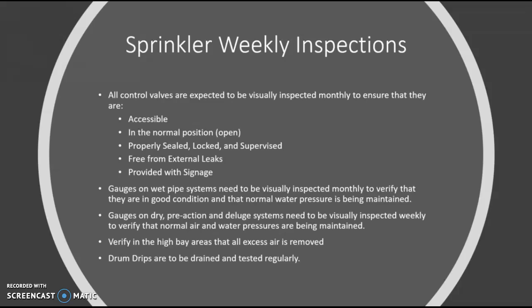And to do this, all the drum drips in the system will have two valves, an upper and a lower. And the upper valve will then be closed. The lower valve will be open to release all the leakage from the system. Make sure that it's clean, debris is out. Close that bottom valve again, open up the primary, and that way the system's back into operation.